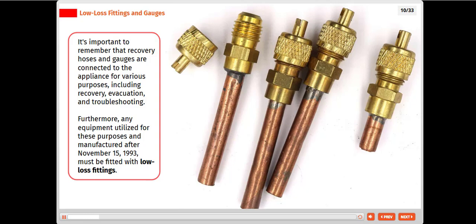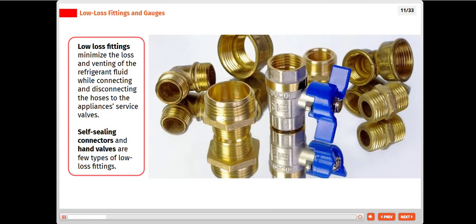It's important to remember that recovery hoses and gauges are connected to the appliance for various purposes, including recovery, evacuation, and troubleshooting. Furthermore, any equipment utilized for these purposes and manufactured after November 15, 1993, must be fitted with low-loss fittings. Low-loss fittings minimize the loss and venting of the refrigerant fluid while connecting and disconnecting the hoses to the appliance's service valves. Self-sealing connectors and hand valves are a few types of low-loss fittings.